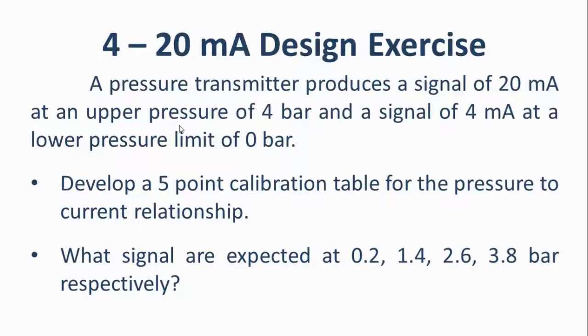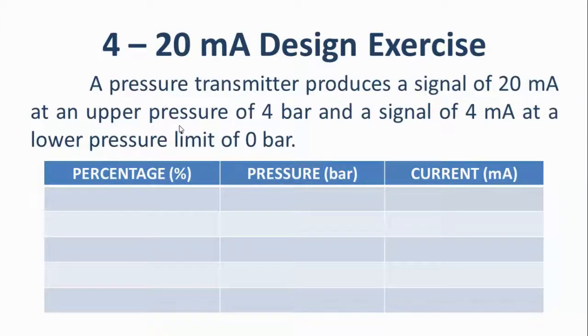We have a design exercise here. A pressure transmitter produces a signal of 20 mA at an upper pressure of 4 bar, and a signal of 4 mA at a lower pressure limit of 0 bar. We need to develop a 5-point calibration table for the pressure-to-current relationship. We'll create a table with columns for percentage, pressure in bar, and current in mA.